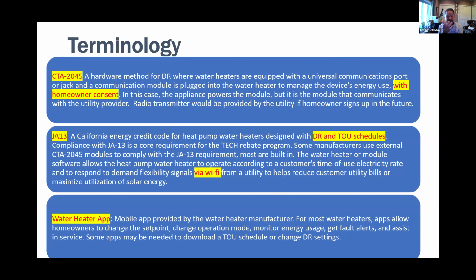Now, I do always remind people, when you're load controlling a heat pump water heater, you're chasing 550 watts of power. 550 watts. And if you happen to be putting mixing valves on them in your state, that means the water heater is already being elevated to a higher temperature in most areas, because if a manufacturer like us is replacing a gas water heater for a homeowner, we're going to tell the contractor to bump it up to 140. That hedges the bet of running out and having a slower recovery with an electric water heater versus a gas water heater, which means it's already thermal storage for the purpose of making sure the homeowner is happy. And that is our goal as manufacturers.